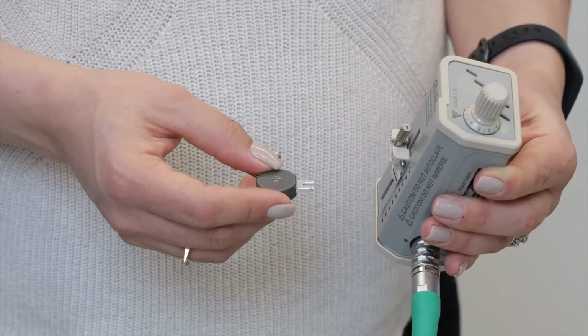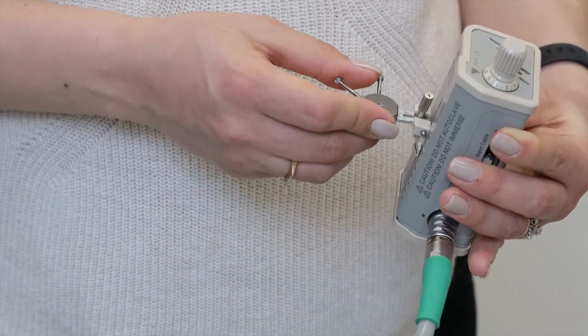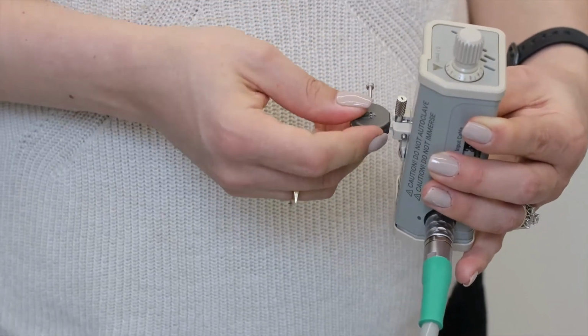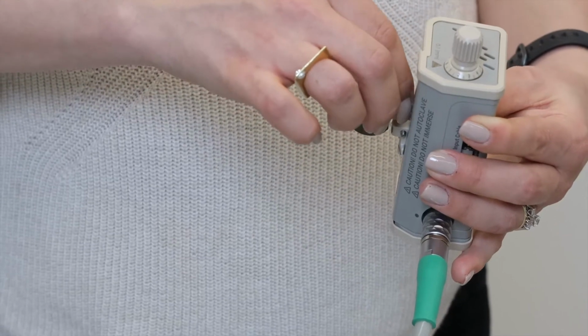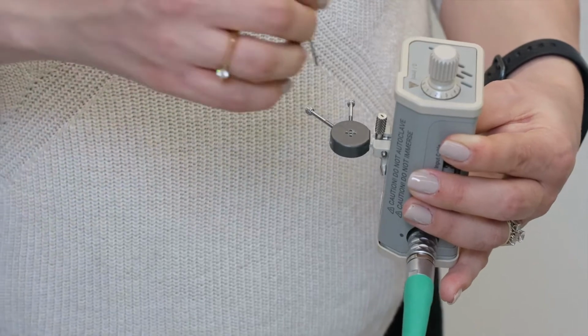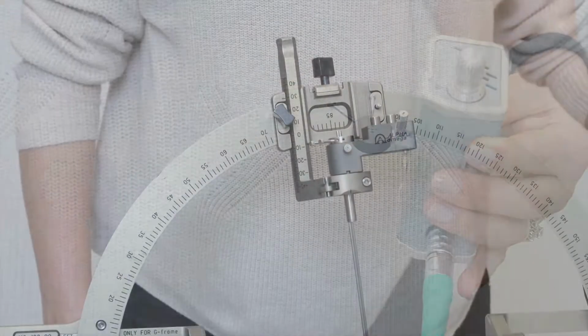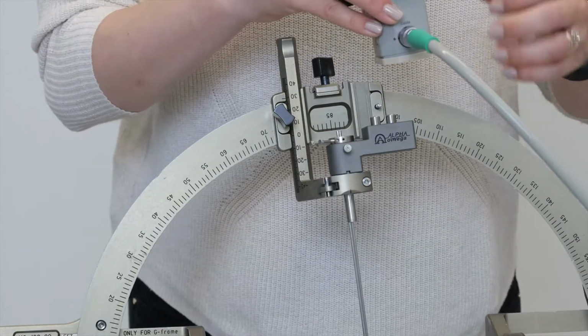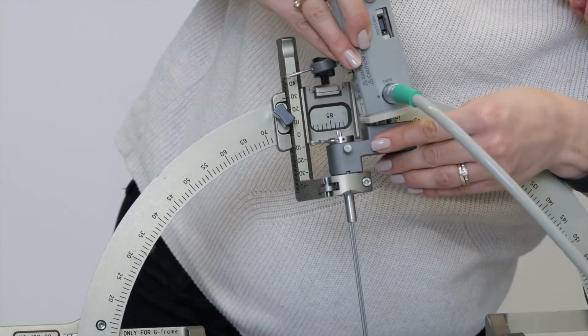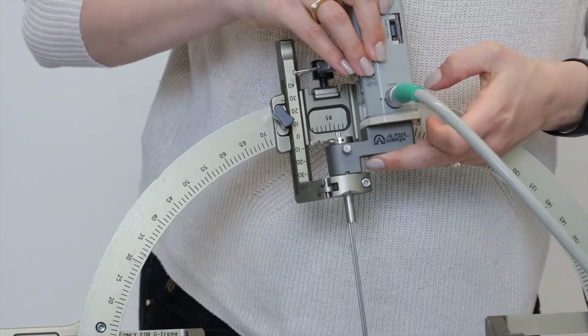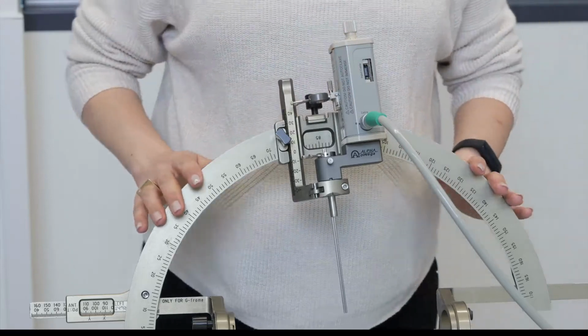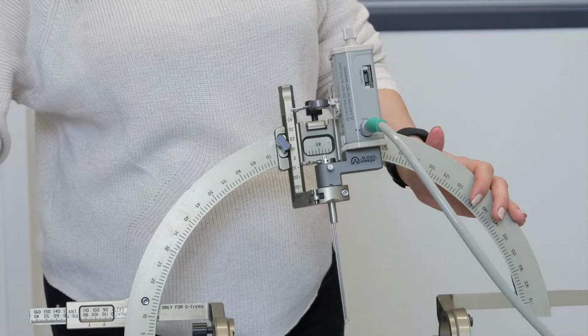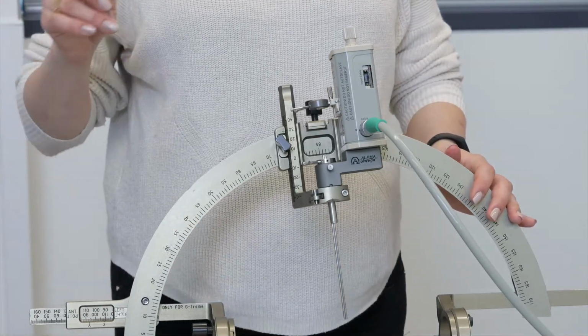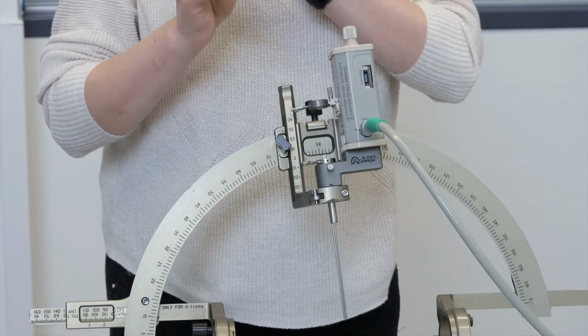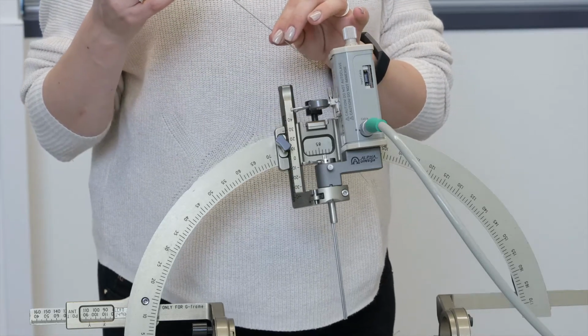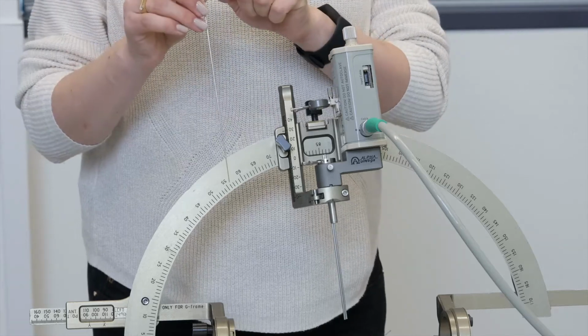Insert the electrode holder either way, making sure you have good access to the screws. You should hear a click once inserted. Tighten the top screw using finger or screwdriver. Place the Headstage on its designated place on the frame adapter. Making sure it's all the way down, tighten well the back screw using your fingers. Take the new electrodes from the sterile sleeve. Make sure that the tip is retracted. Alpha Omega standard neuroprobe length is 237 millimeters from the micro tip to the stopper.